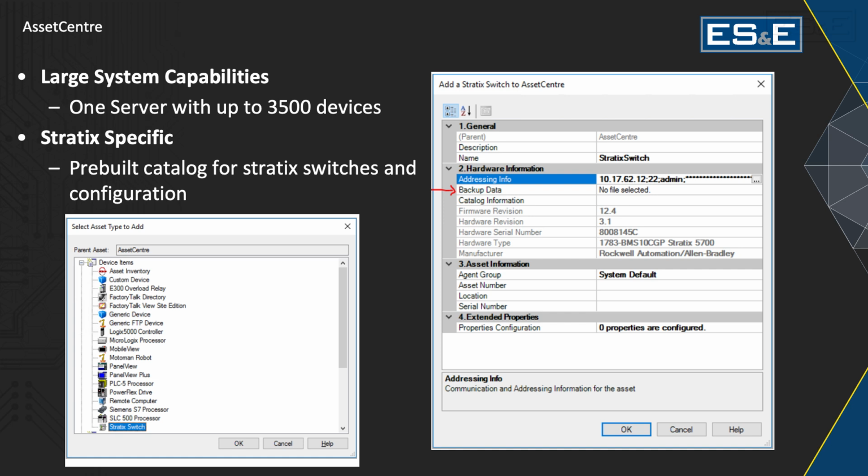And it also allows you to do automated disaster recovery. So occasionally it will go out and it will interrogate controllers and get the latest version from them. And it does that on an interval that you specify. And it will do a comparison against the version that you have pinned, what we would call the primary version, against what it finds out in the facility that's currently running. And if there are any deviations, it will notify you of those deviations.